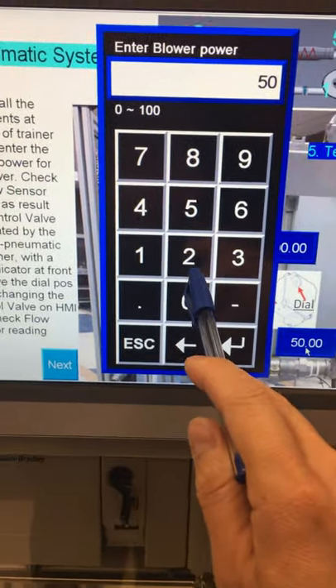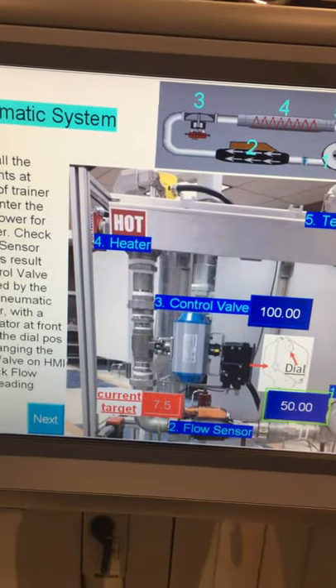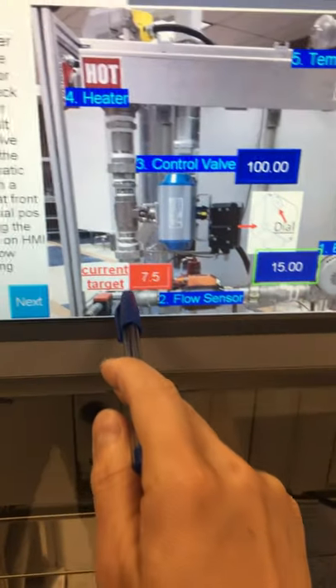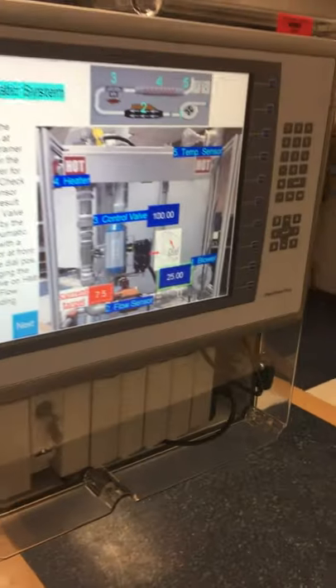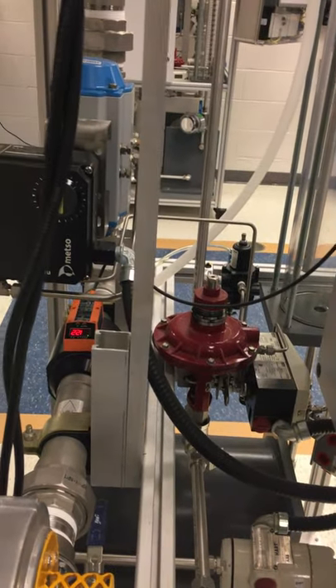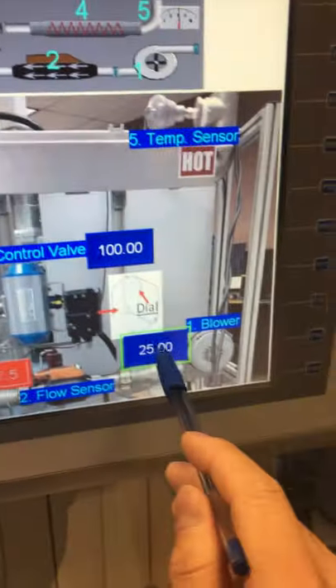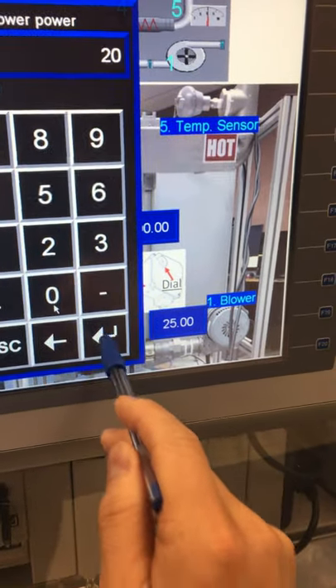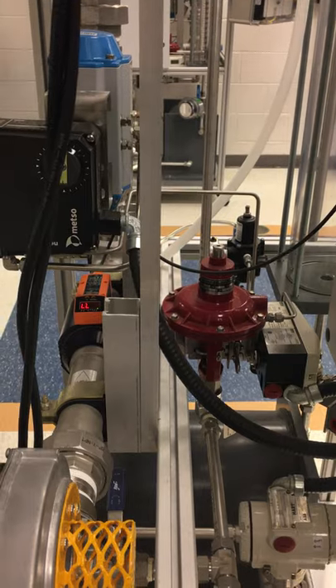So 50%, right? We can change to maybe 15% on the blower. The target you can see here, we are trying to get 7.5. And if we look at the back, it's zero, so it's too low. We need to increase that. So 25% on the blower. I'm reading the flow sensor at 12 point something. We need to get 7.5. So either reduce the blower percentage a little bit, maybe 20%. Let's see if we can move on there. Right now I'm reading 7.7. You can see on the orange, 7.5. That's good. That's really good.